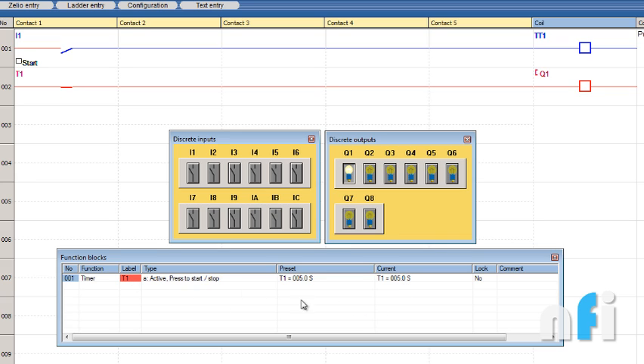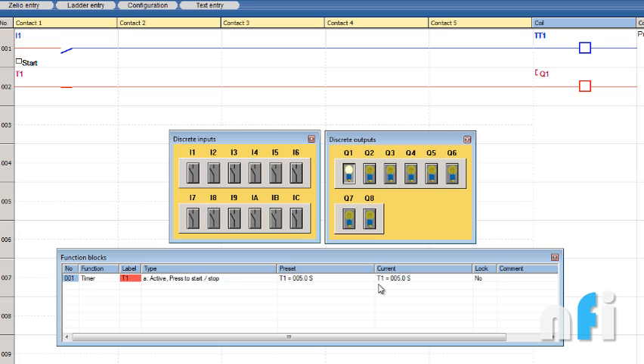I'll just press and release. It has started counting and after five seconds it will turn on T1, which will turn on output Q1. That's how you can use this timer. If you're using a push button to give a delay, you should use this one, 'Active press to start.' If you're using a toggle switch to give a delay, you can use the first one. But this pulse type is used only if you have just one pulse as input to latch the timer. This is a special type of timer.